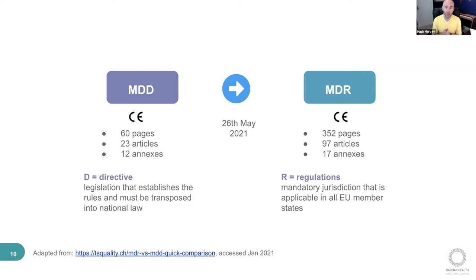So if you are new to the European market, you must go through this MDR process. If you are a manufacturer who managed to get regulatory clearance before the 26th of May, you may have an MDD certification or CE mark. That doesn't mean you've got away scot-free. You still have to do MDR by 2024, so you still need to catch up and do it.